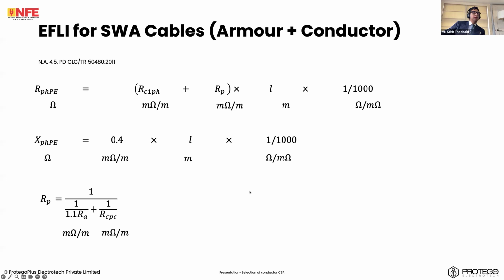Yeah, there is a mistake in this slide. Let me just correct it. There is a 1.1 that has come in twice, which was not supposed to be the case. So here we do not multiply by 1.1. Here I'll show you why. We take simple line plus the parallel, the overall impedance, the overall resistance of the parallel conductor plus the armor. The 1.1 has only been multiplied by the value of the armor, not the actual parallel conductor that is running.